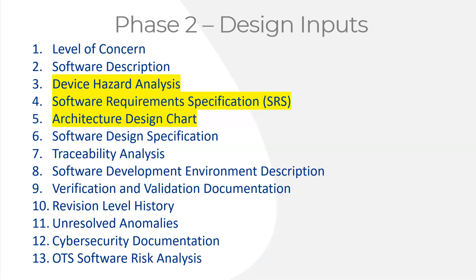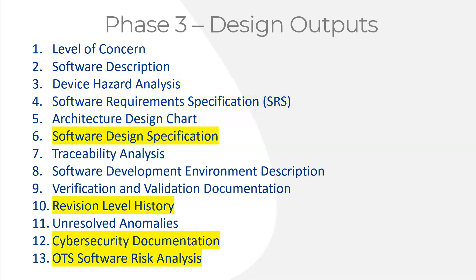Once you've developed and approved the design inputs — and FDA requires formal approval of design inputs — you move to the development phase, which is usually the longest and most iterative phase. Those familiar with agile development and sprints will recognize this iterative structure. Every time you try to develop and compile a unit module for your software, you may encounter an error. If you have an error, you go back, change the code, and run it again. That iterative process gets fully documented — you want to document every single time you go through it.